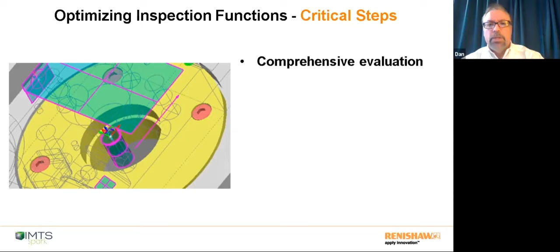Those measurements need to be traceable. And the traceability comes through an artifact or through calibration of the machine. That's really the benefit of a coordinate measurement machine in a company, that it's your traceable reference standard that you can use to check things, to verify that a measurement indeed correlates with all the other measurements taken around the world. So: comprehensive evaluation of the part, traceable measurement, and we want it to be fast. We can't afford to wait to get information on what's going on with these parts. So even though we may not be using it directly for controlling tool or work offsets on a machine, we still don't want to be waiting long periods of time to find out what's going on comprehensively with the part we produce. The instruments need to be reprogrammable.